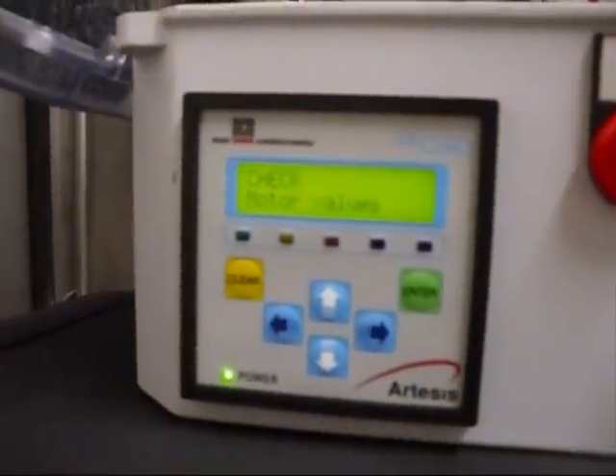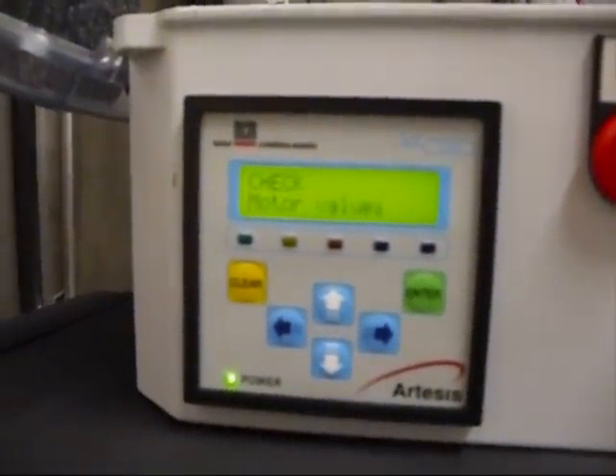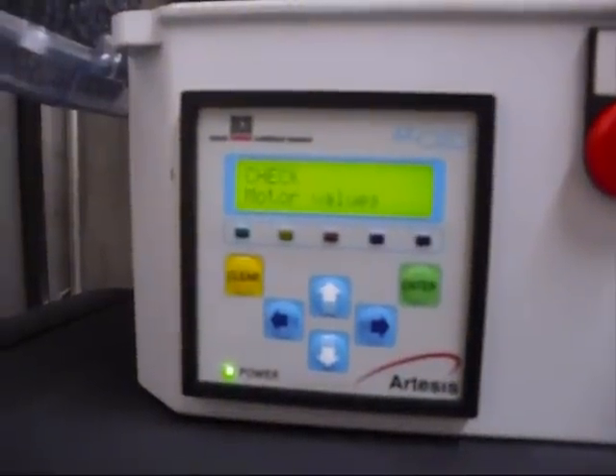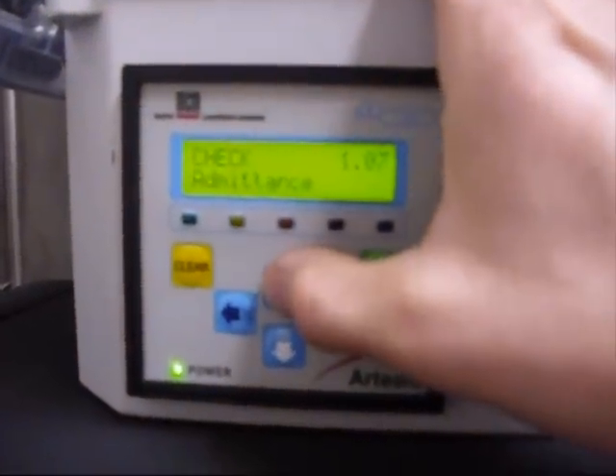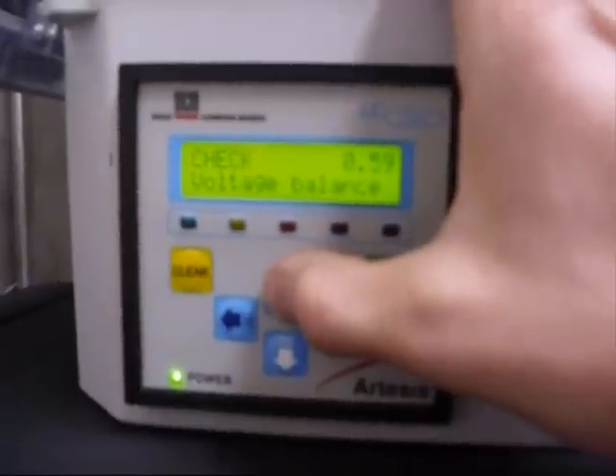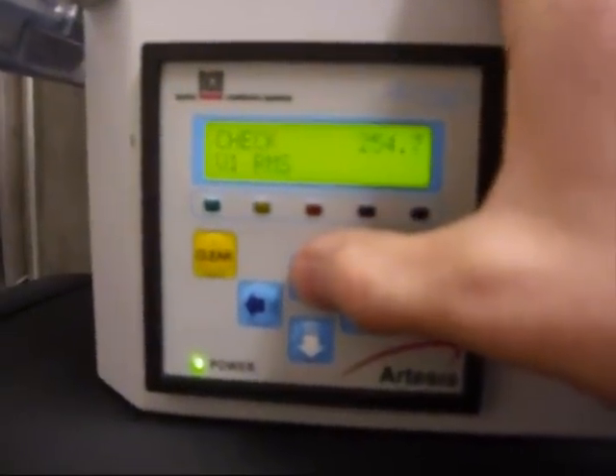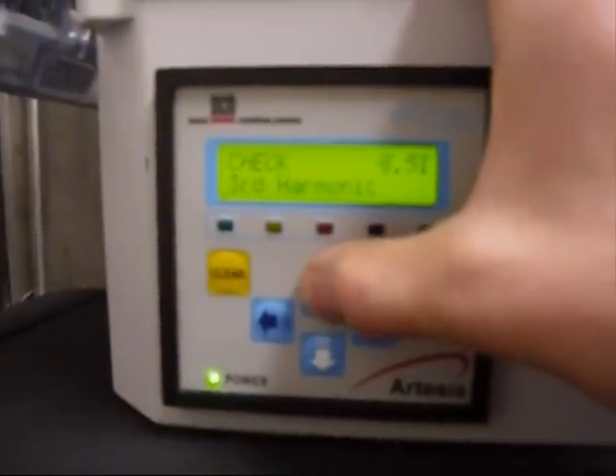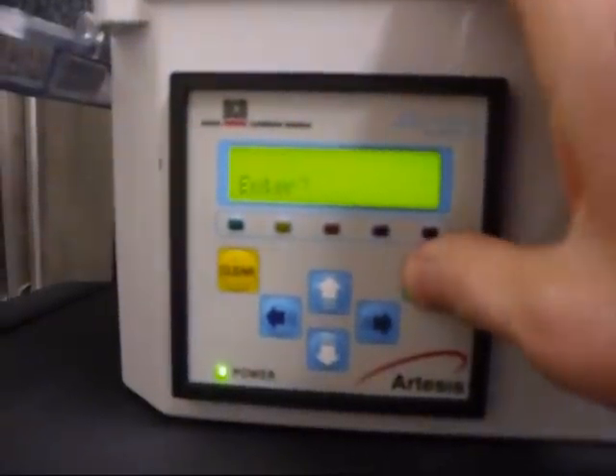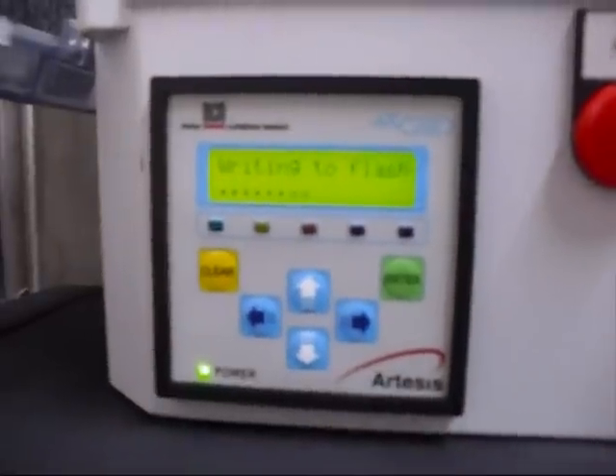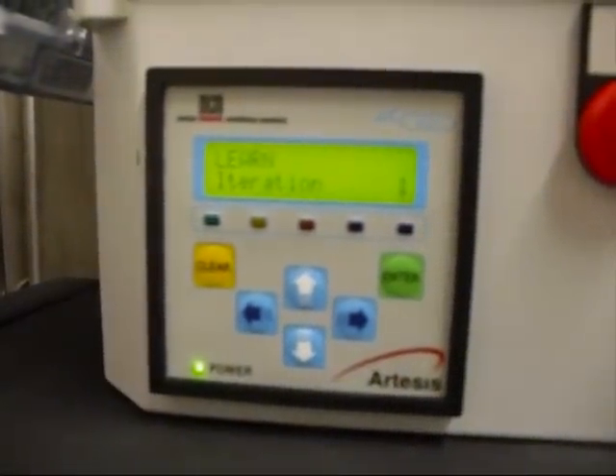The unit has finished the check motor sequence. We can see that it comes up, assuming that it completes the sequence correctly, with check motor values. Now we can check what these values are by scrolling through. If we use the up arrow, we can see that our power factor is pretty good. We've got active power, voltage balance and current balance, voltage and current readings, and then our harmonics. So if we clear and go back to the main screen, the next stage is to put this into learn. So we press the up key twice and we press enter, enter. The unit is now learning.